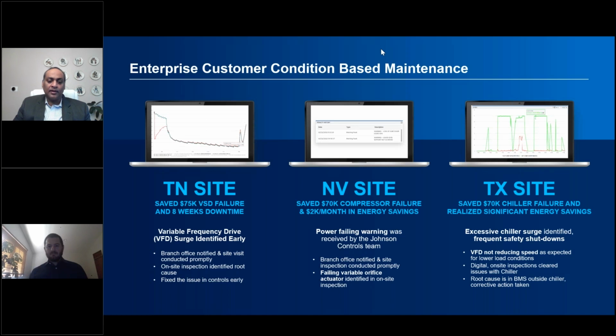Here's an example where our chiller expert team detected a chiller surge happening, and the data on the computer screen shows it very clearly. There's a surge happening, and that surge was real. When they caught it, they quickly activated the branch to go check it out, and they caught the issue before it became a problem, correcting it and preventing a VFD from failing on the chiller.